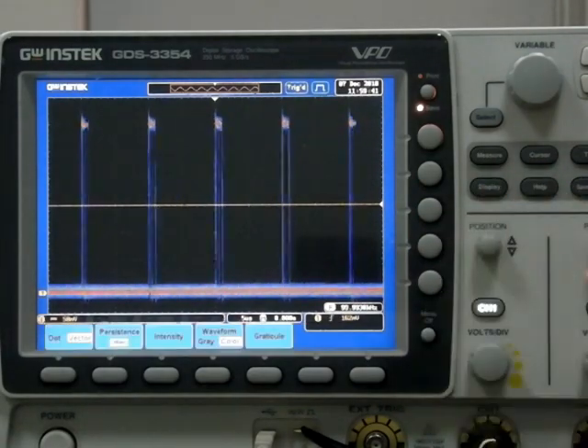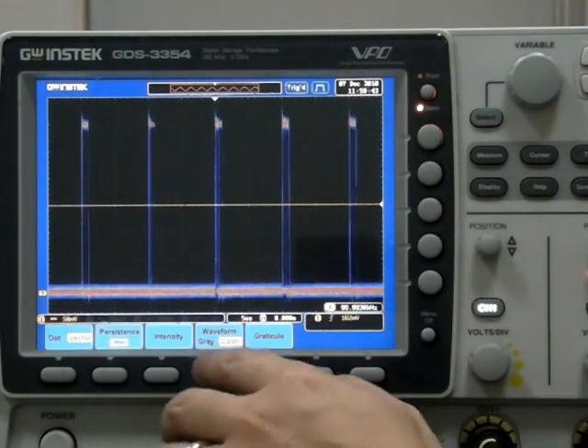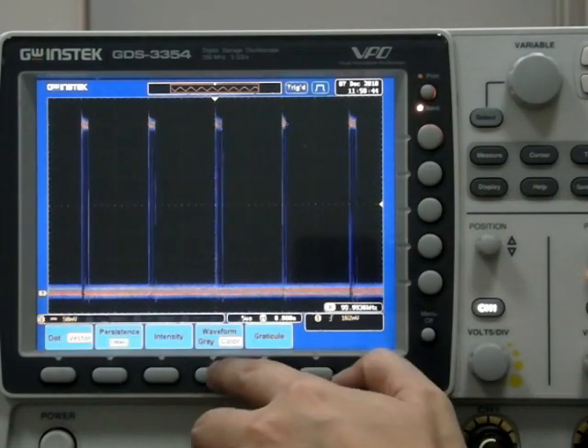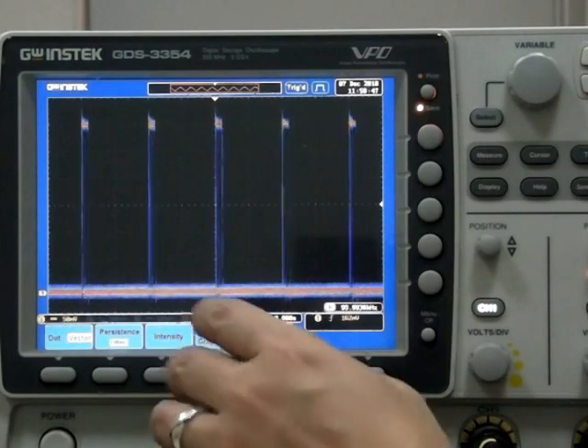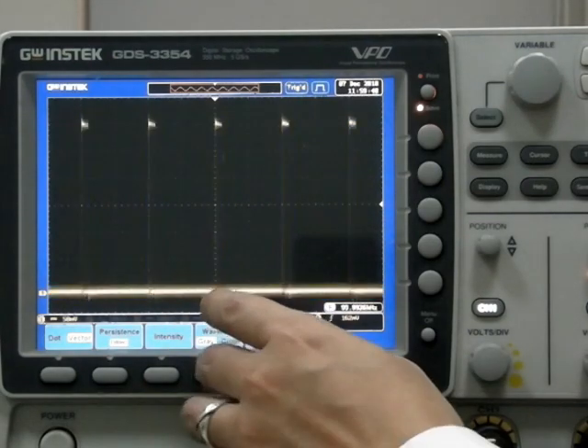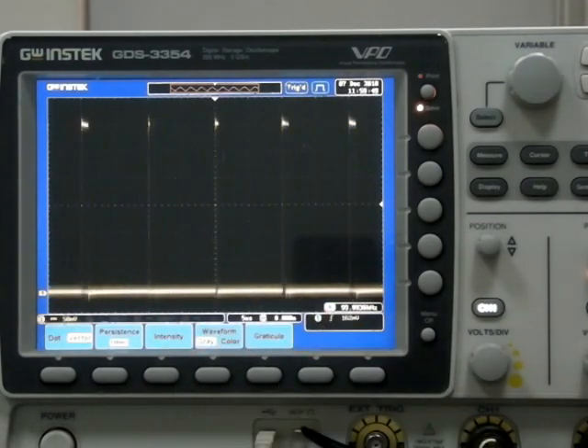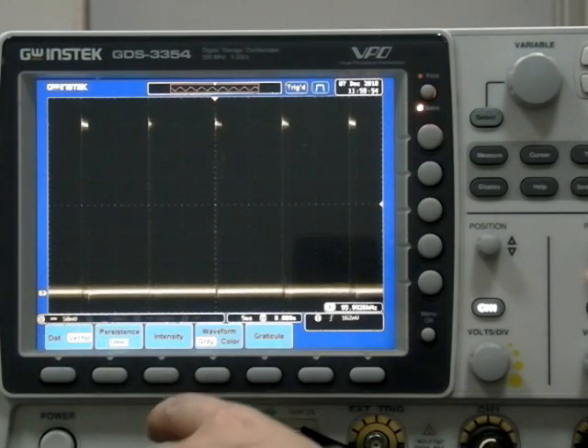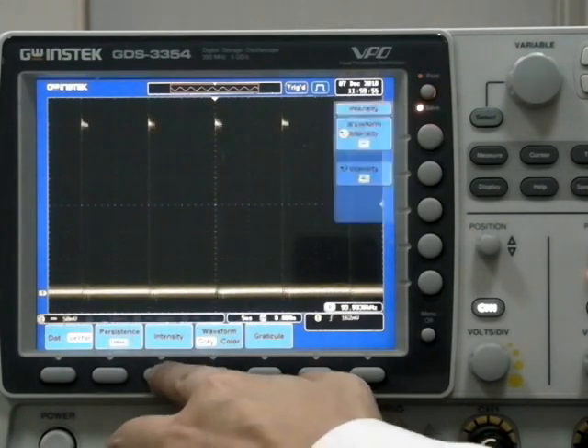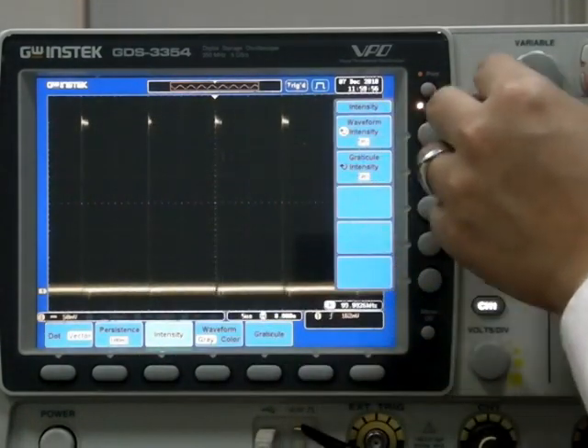Press the Display button and set Waveform on the bottom of the screen to grey. Next, select the Intensity function on the bottom menu screen and adjust the Intensity with the Variable knob on the front panel.